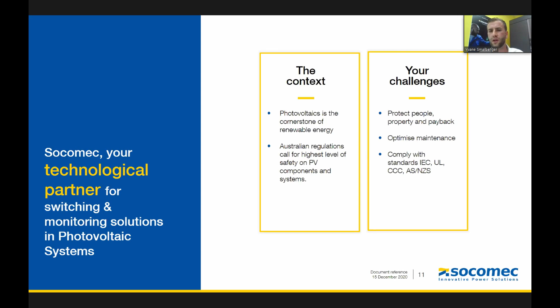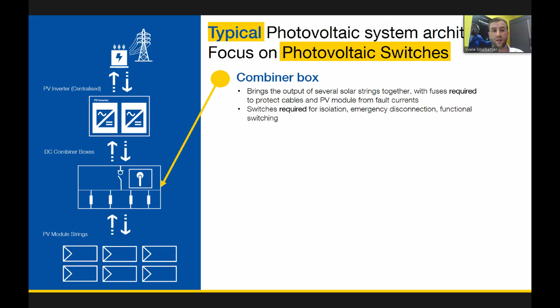When we focus on combiner boxes, a combiner box in the system on the left, so we have our PV strings, which feed into a combiner box and then goes to my PV inverter. The combiner box, just as a quick overview for those who are not familiar, it brings together the outputs of several strings into one box where we provide fusing to protect the cables and the PV modules from fault current, and also provide isolation, emergency disconnection, and functional switching for this part of the system.